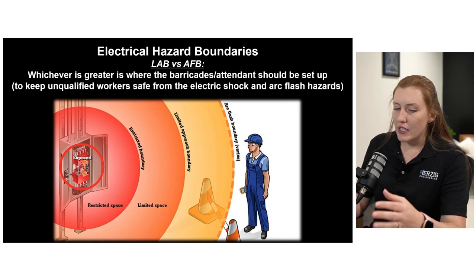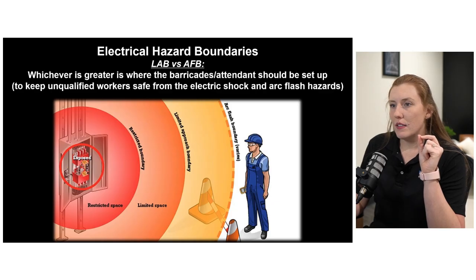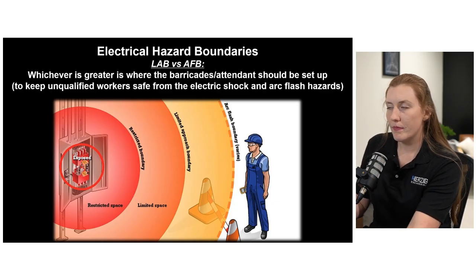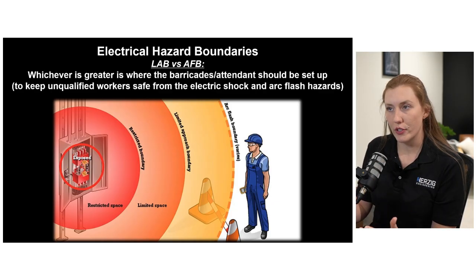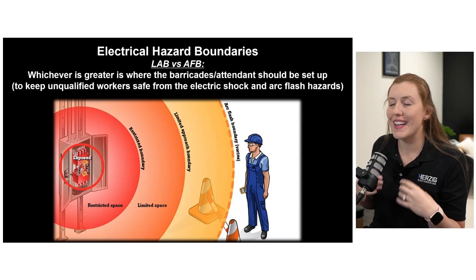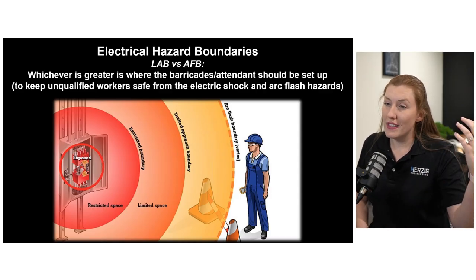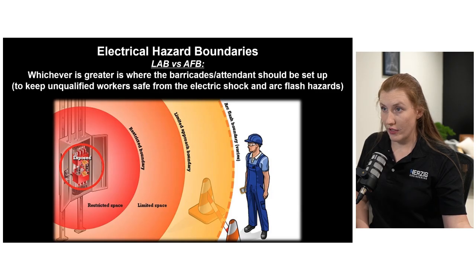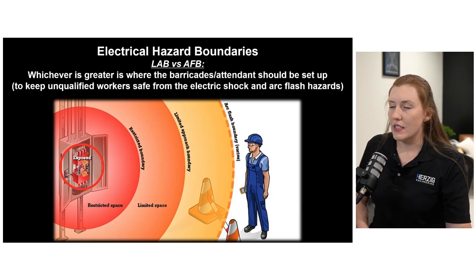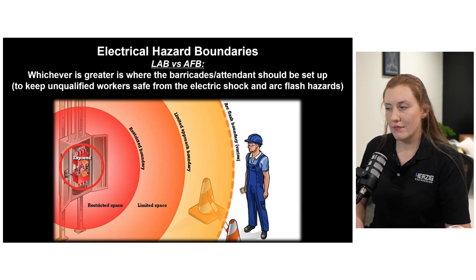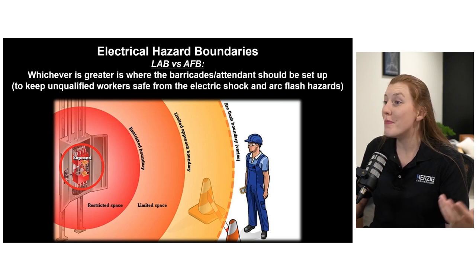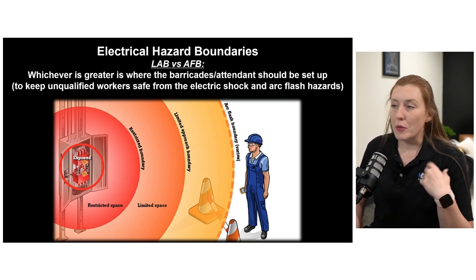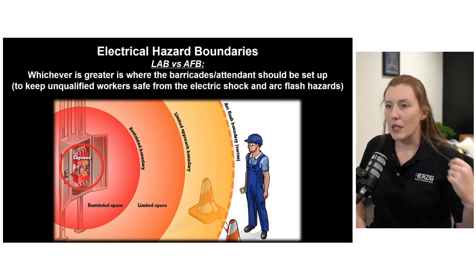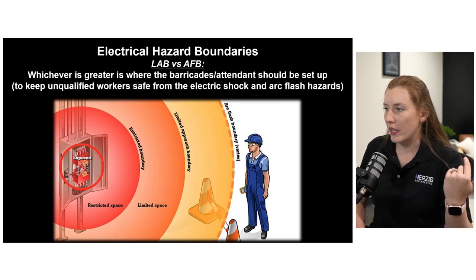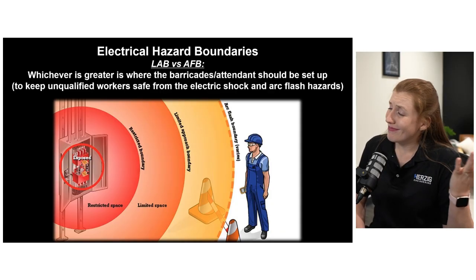I'll get into this very briefly in a moment, but this is the bare minimum - I always say add a foot or two. Whatever the furthest boundary is, add a foot or two, because if it's the shock boundary that's the furthest, if you look at the distance, it's really only 3.5 feet. That's barely enough elbow room - make it 5 feet. For medium and high voltage stuff it's further, sure, but for low voltage, the vast majority of applications, 3.5 feet - let's bump it out to 5.